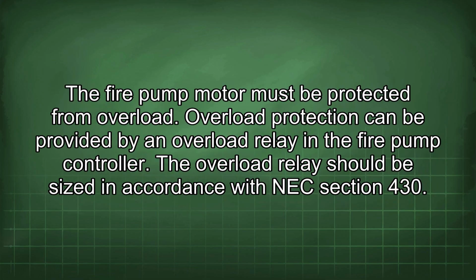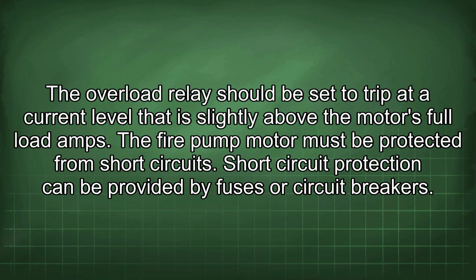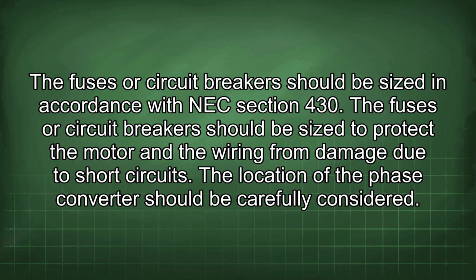The fire pump motor must be protected from overload. Overload protection can be provided by an overload relay in the fire pump controller. The overload relay should be sized in accordance with NEC Section 430. The overload relay should be set to trip at a current level that is slightly above the motor's full load amps. The fire pump motor must be protected from short circuits. Short circuit protection can be provided by fuses or circuit breakers. The fuses or circuit breakers should be sized in accordance with NEC Section 430. The fuses or circuit breakers should be sized to protect the motor and the wiring from damage due to short circuits.